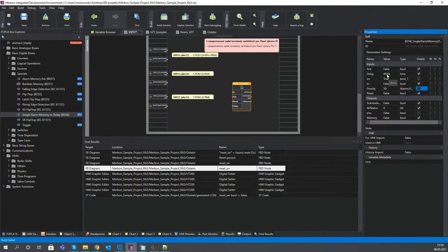Okay, 30 seconds is okay for the most of the applications like HVAC units, fan control, flooding of a heat plant, and so on, pump checking, everything. Maybe if you have a fire alarm, then 30 seconds is not a good idea. So then it could be set to 0. But anyway, I can put it in again and it's not visible.